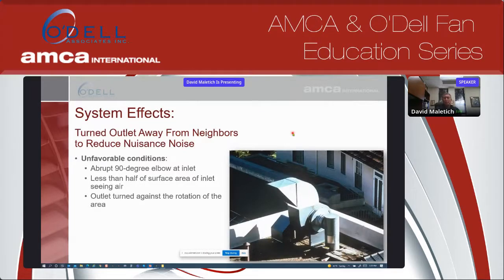A lot of times system effects are a result of issues that are out in the field. So they put this 90-degree elbow here. They're getting noise complaints from the neighbors over in this area here. They put a position C elbow on the discharge of the fan, so air comes out, deadheads up against the top, and has to get reaccelerated out this direction. Fairly significant losses at this point.